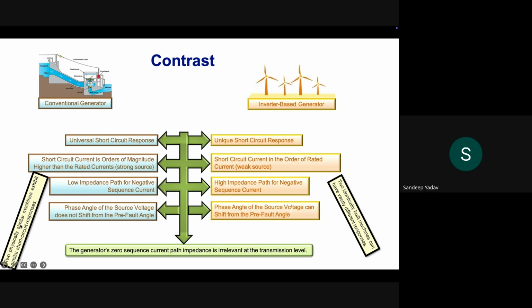So two physically similar machines exhibit similar short circuit responses in case of conventional sources. However, in case of inverter-based resources, two generators of different manufacturer, two inverters from different manufacturer may have very different or significantly different short circuit responses or short circuit behavior.